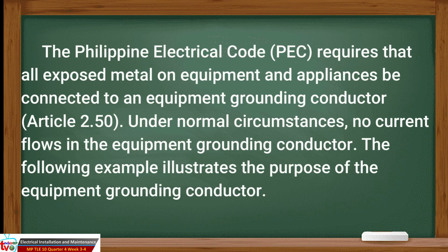The Philippine Electrical Code requires that all exposed metal on equipment and appliances be connected to an equipment grounding conductor according to Article 2.50. Under normal circumstances, no current flows in the equipment grounding conductor. The following example illustrates the purpose of the equipment grounding conductor.